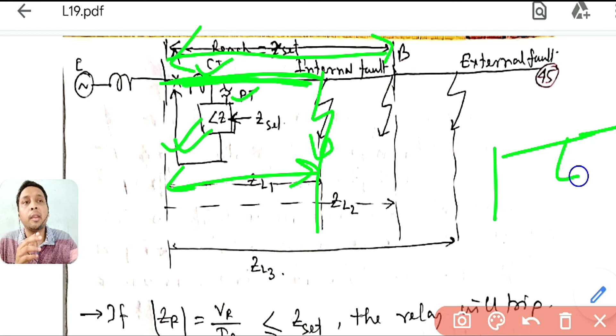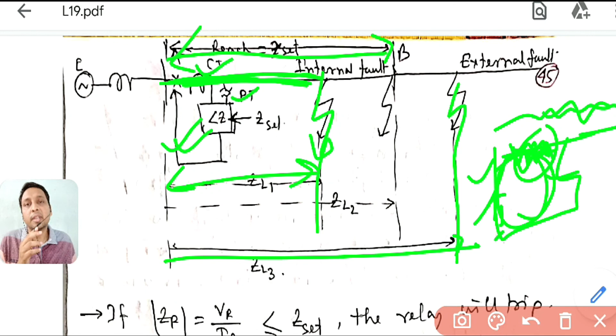Total length was 10. Now you know the circuit is something like that. Because the current is not going through the entire line, it is closed by here because the fault is here. So what will be the impedance? This impedance is less than your total impedance, because you are doing V by I for this circuit. So for this circuit, if you do V by I, you will get a less Z compared to the Z set value. So if it goes less than that, then it will trip. If the fault is external, if it is outside, then your ZL is more than your Z set, then it will not trip. So the reach is fixed here.